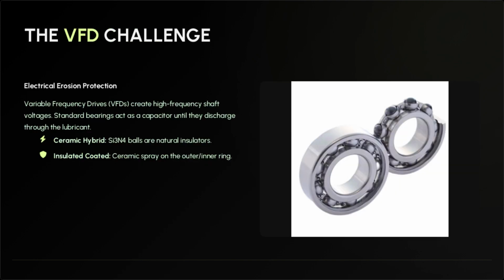In 2026, variable frequency drives are everywhere, but they come with a hidden danger: shaft voltage. These voltages can jump across the bearing, causing microarcs that destroy the lubricant. To solve this, engineers use ceramic hybrid bearings or insulated coatings to break the electrical path and stop the discharge.